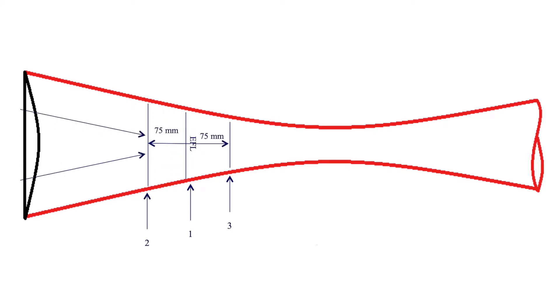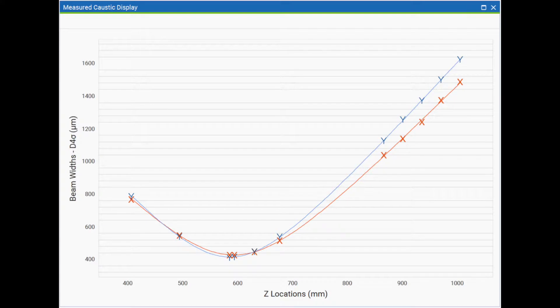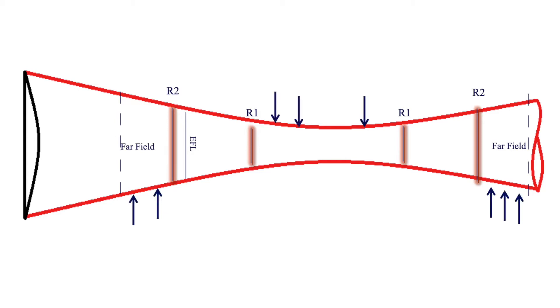This new Beam Squared feature identifies these locations by first finding the beam waist and Rayleigh range. It then calculates proper measurement locations along the beam's propagation or caustic. Here is a representation of the X and Y beam widths versus the distance from the focusing lens. Beam width measurements are taken at one Rayleigh length about the waist, then more are taken past the second Rayleigh length in the far field.